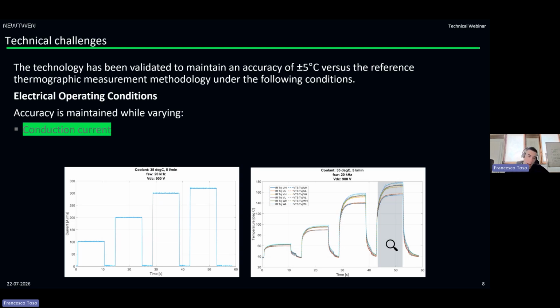And on the left, you will see the current emission profile, in particular the RMS profile of the current during this 1 minute of operation. At the top, you can see the coolant, the switching frequency and the DC bus voltage condition. So for example, in this test, we had 35 Celsius degree of coolant temperature, 5 liters per minute of coolant flow rate, 20 kilohertz of switching frequency, and 900 volt of DC bus. And on the right, you can see the step response, basically, of the temperature with the current.